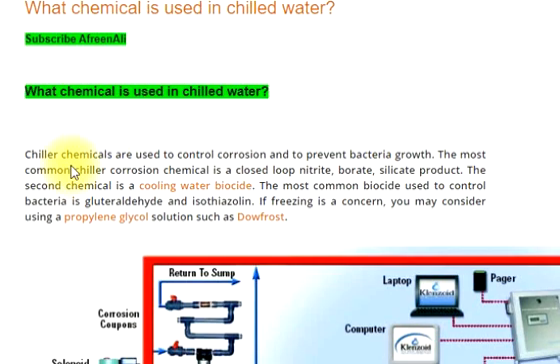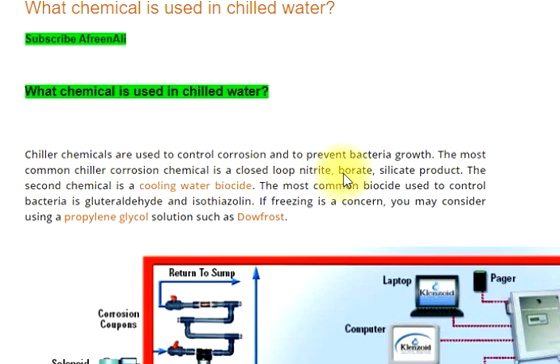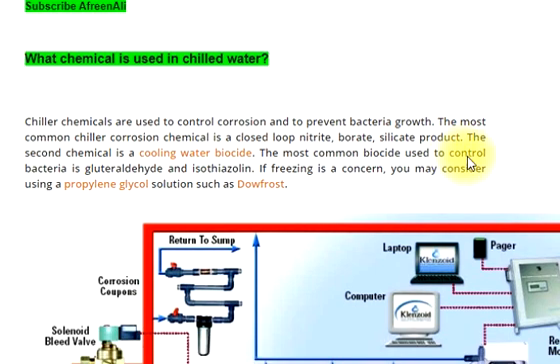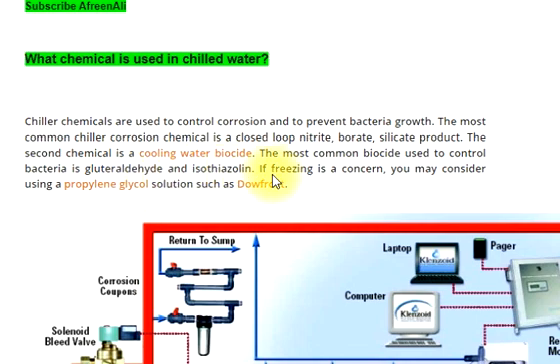Chiller chemicals are used to control corrosion and to prevent bacteria growth. The most common chiller corrosion chemical is a closed-loop nitrite or a silicate product. The second chemical is a cooling water biocide. The most common biocide used to control bacteria is glutaraldehyde and isothiazolin.